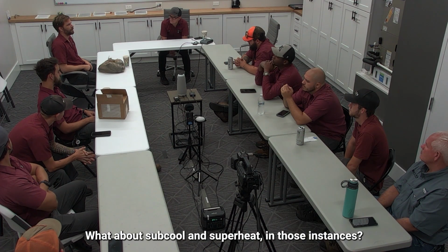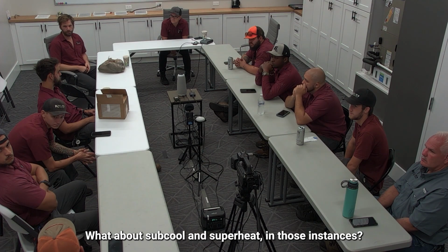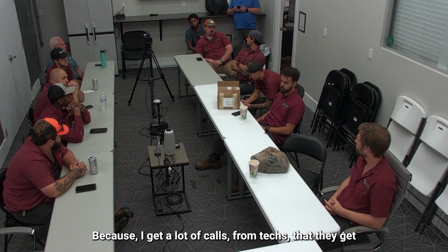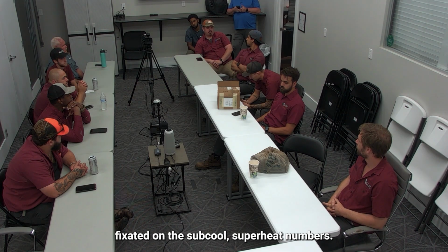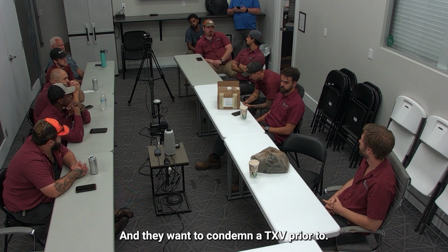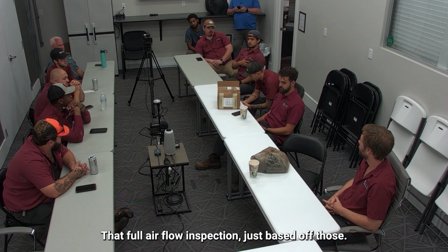But what about subcool and superheat in those instances? Because I get a lot of calls from techs that they get fixated on the subcool and superheat numbers, and they want to condemn a TXV prior to that full airflow inspection, just based off of those. Yep, that's good. You have subcool maybe that's a little bit lower, and typically your superheat's a little bit lower on a cold house too.